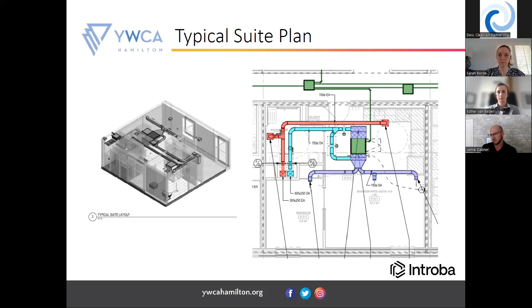The other thing you see here that's a little different than regular projects is the outdoor air bypass. The blue duct going into the back of the fan coil can actually go right into the supply ducts, and you can turn the fan coil off in the shoulder seasons. This way we could save quite a bit of fan energy and not need that fan running to circulate air within the suite. You can just run the ERV on the roof. Think of it like a free outdoor air ventilation bypass.